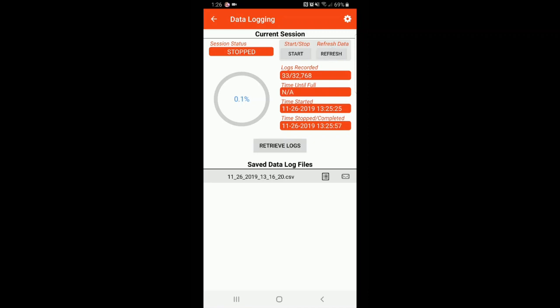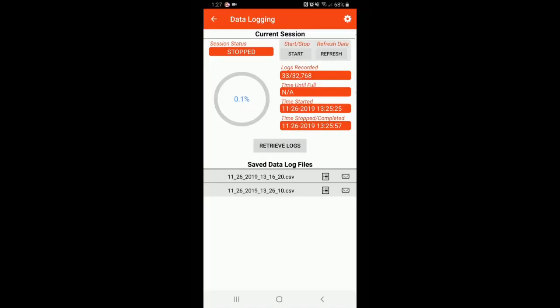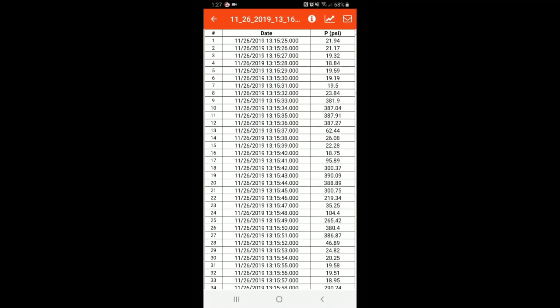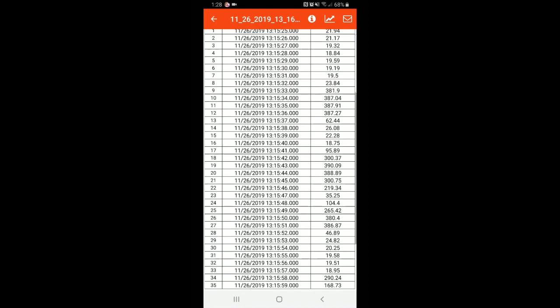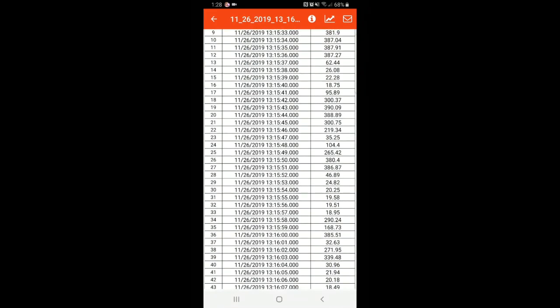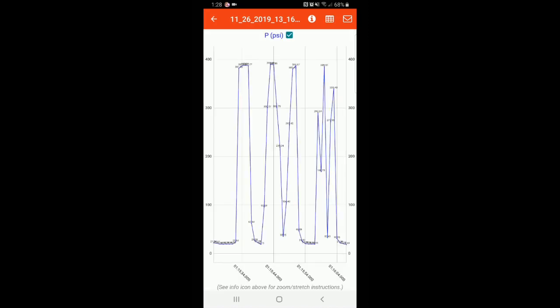Once it has been stopped, you have the ability to then go in and retrieve these logs. You can change the name of the file, or it will give it a default one based on the date and time. Once the log file has been created, you can open it from this same window. When you open it, there are numerous ways that the pressure values in the log can be displayed. As we have this set to 1 second intervals, you can see the pressure changes in the right hand column, the date and time in the middle, and the number of the log down the left hand side. You can scroll the whole way to the bottom, or by means of the selection in the top right hand corner, you can also view this in a graph format.